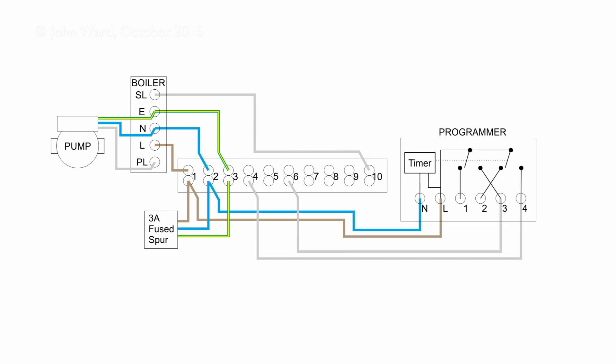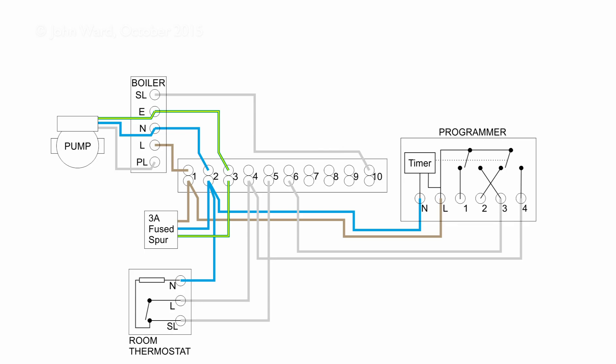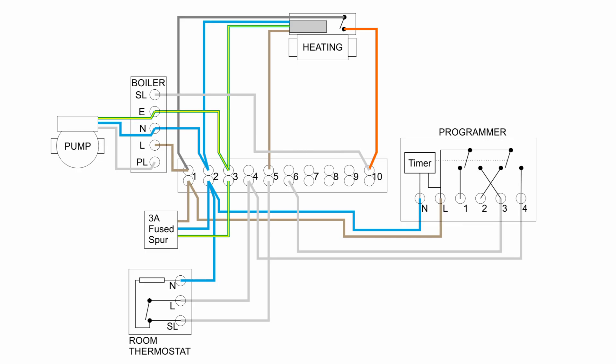Now let's look at the heating side, which is extremely similar. The first additional item needed is a room thermostat, which senses air temperature and has three terminals — one is a neutral for the internal anticipator heater or electronics. Like the cylinder thermostat, it's a two-contact switch: open when heat isn't required, closed when the room cools and heat is needed. The heating valve is exactly the same type as used for hot water — only plumbed into the radiator pipes. It has line, neutral, and earth on the left, a brown wire for the motor, and an orange wire that activates when the valve has fully opened via the switch inside.